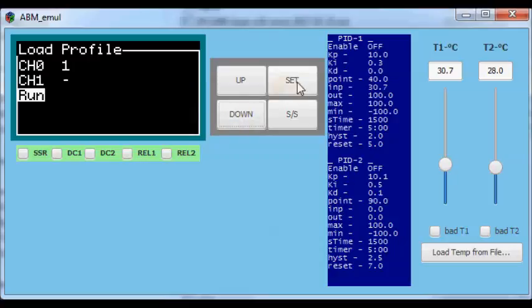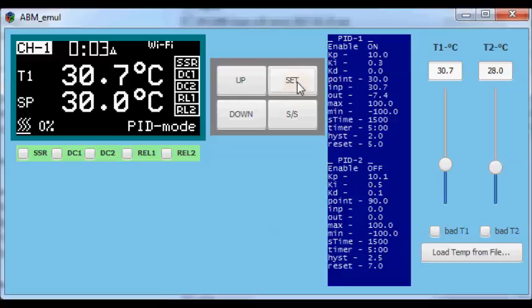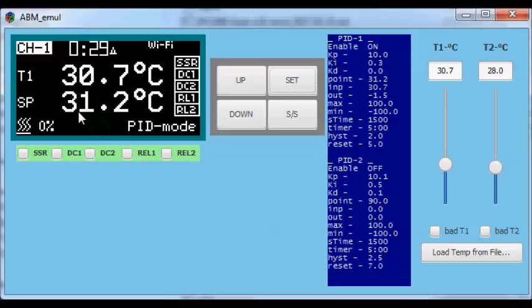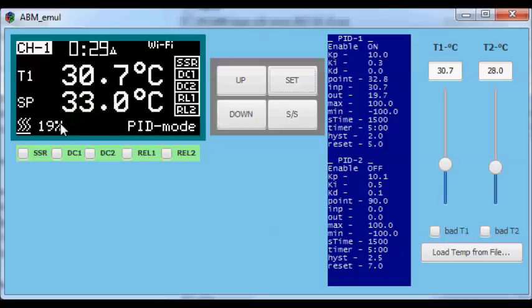Once you have done the association, you can enter the run mode. The first setpoint was 30 degrees, kept for 30 seconds. The timer starts and you will see when the counter reaches 30 seconds the ramp will begin. In this case, by chance, the current temperature T1 is already over this point, so the output is zero. We reach the end of the soak time and the ramp starts — now the temperature will be increased from 30 to 40 degrees in 30 seconds.